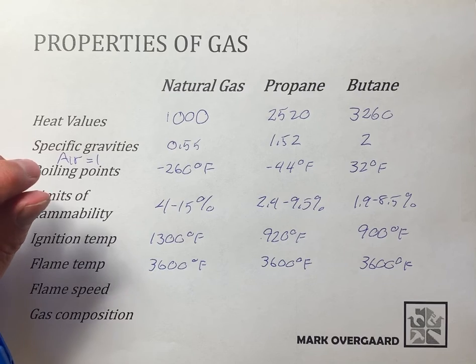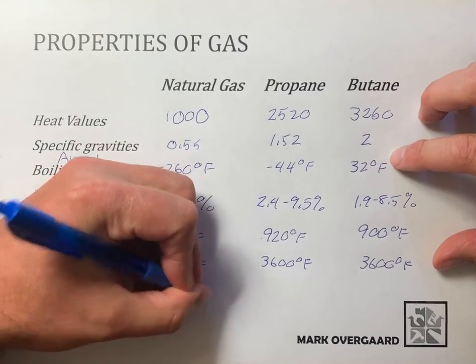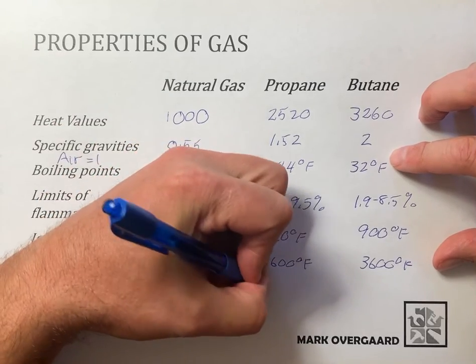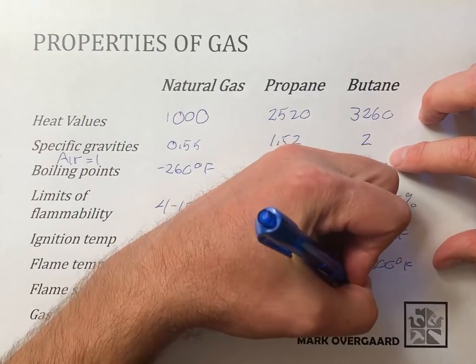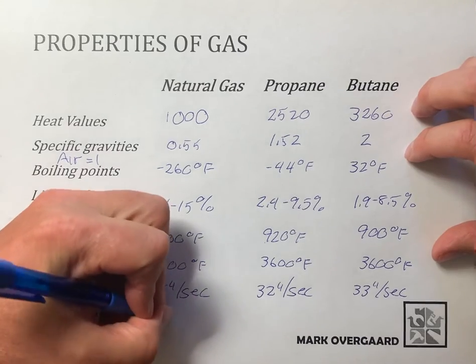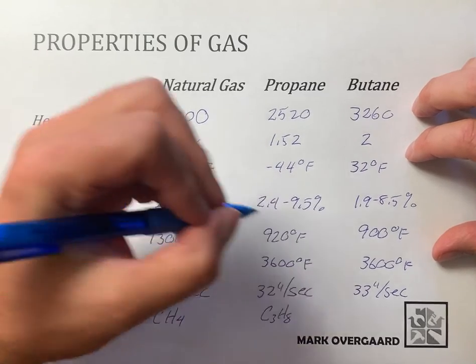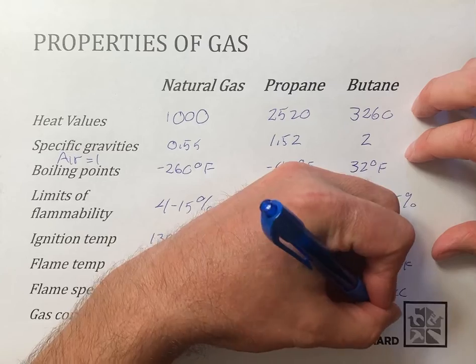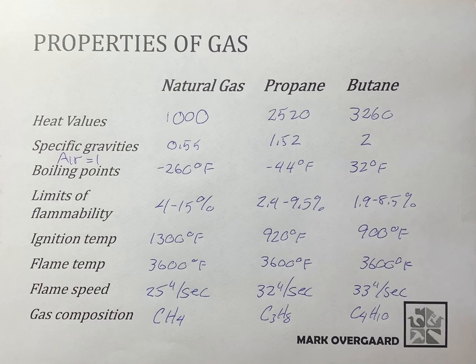Flame speed — how fast does the flame burn back toward the source? For natural gas it's 25 inches per second, propane is 32 inches per second, and butane is 33 inches per second. Last but not least, gas composition — we already covered that: natural gas is CH4, propane is C3H8, and butane is C4H10.